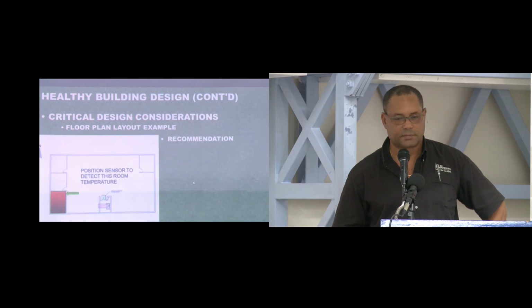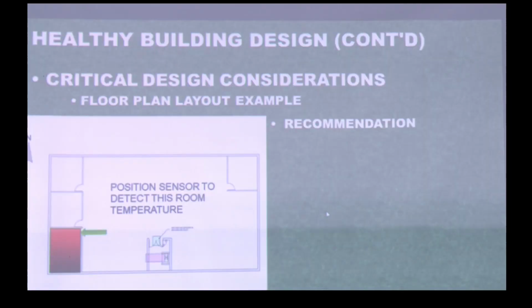So he's going to suffer. The recommendation is to make sure that you're sensing the temperature in that room. That's your heaviest load, and your system's going to react to that. Then you can balance the rest of your system so that everybody else feels comfortable. But if you can't satisfy the heaviest load, somebody's going to be unhappy.